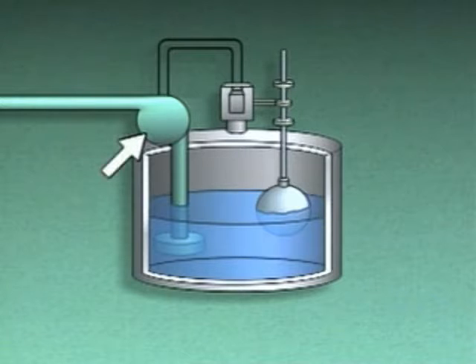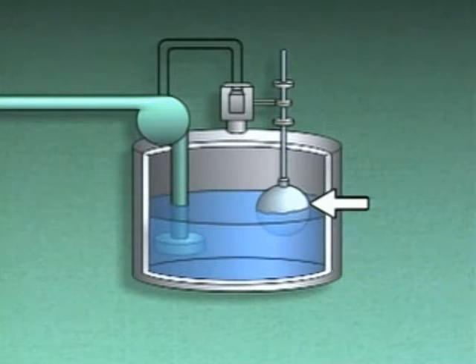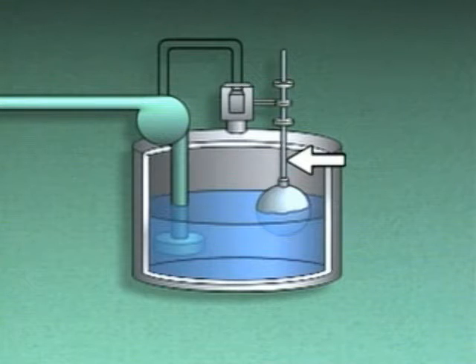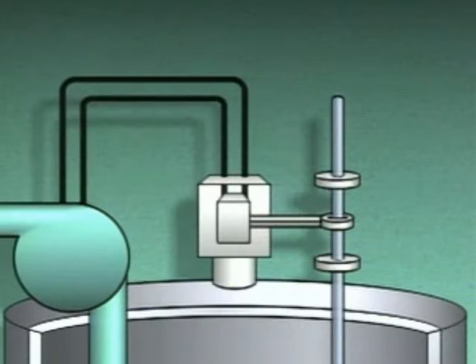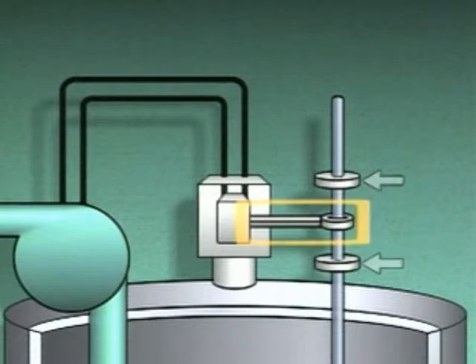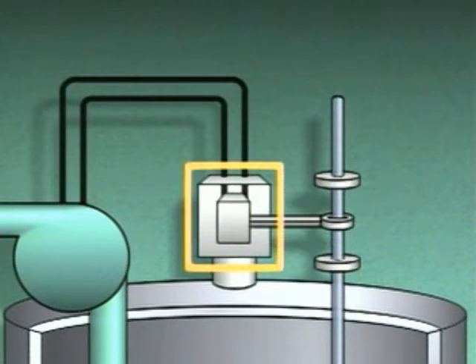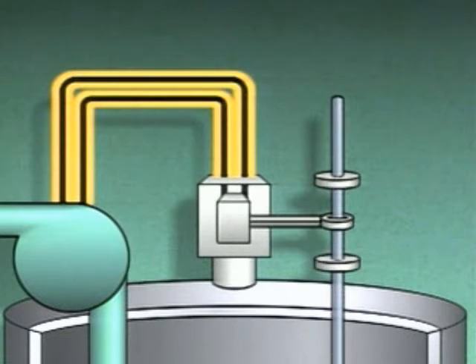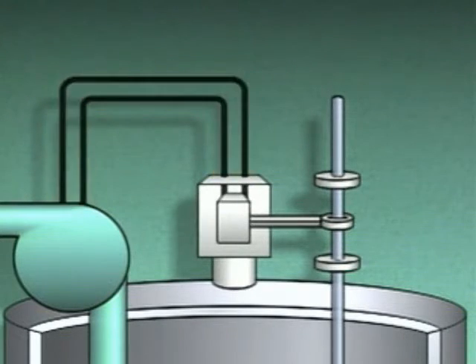To see how two-position control works, let's look at an illustration of a sump pump arrangement. In this system, a pump draws water out of a pit or sump. A float with a rod is the sensing element in the system. The float rod has two collars, which serve as stops for a linkage that connects the rod to a switch.